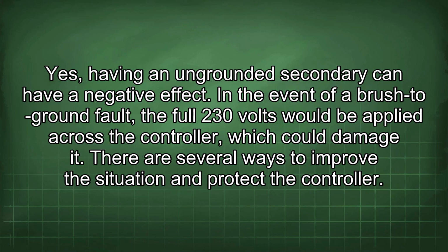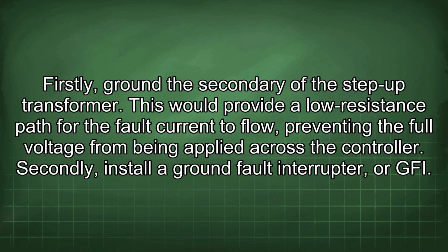Yes, having an ungrounded secondary can have a negative effect. In the event of a brush to ground fault, the full 230 volts would be applied across a controller, which could damage it. There are several ways to improve the situation and protect the controller. Firstly, ground the secondary of the step-up transformer. This would provide a low resistance path for the fault current to flow, preventing the full voltage from being applied across the controller. Secondly, install a ground fault interrupter, or GFI.